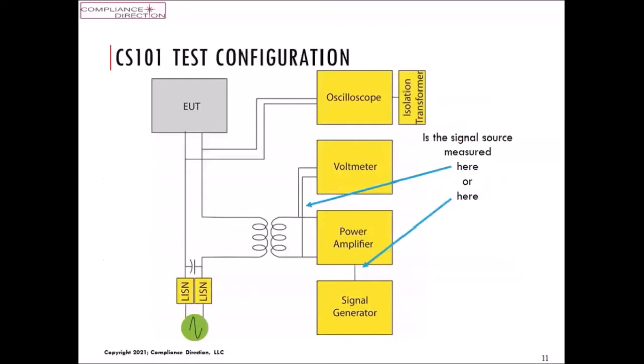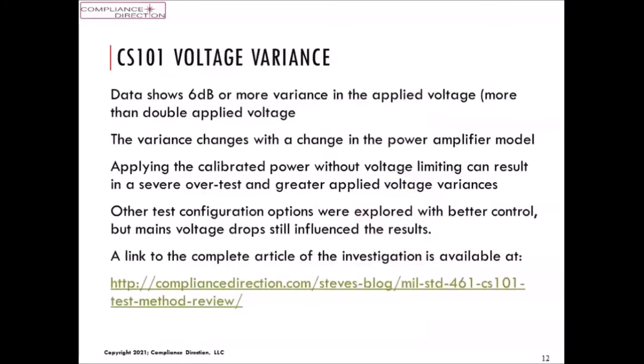When it comes time to do the test, we couple the signal here, and the question comes up. Do we measure the signal source at the voltmeter, or do we measure it at the signal generator? A lot of laboratories simply set the power amplifier up during calibration, record what the generator says, and then play that back. They can end up overdriving the system depending on the EUT performance, overtest significantly, and the voltmeter reading allows you to change the gain. So this question came up during a discussion a couple of years ago now, and we've been studying it a lot since.